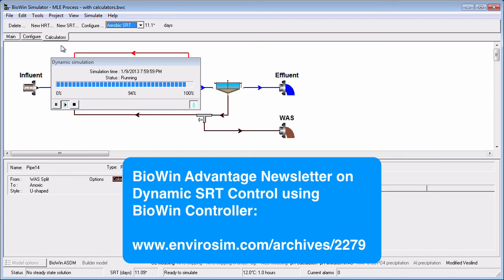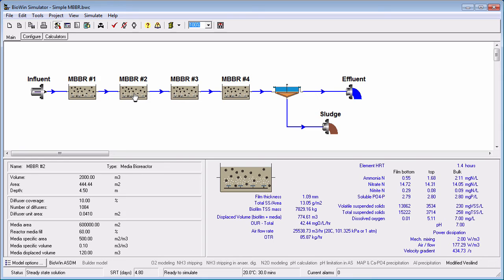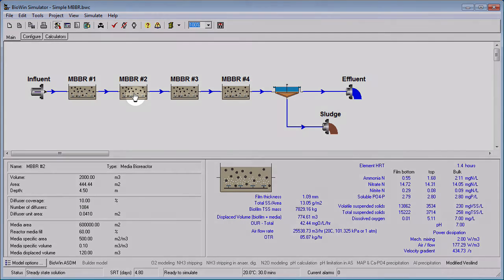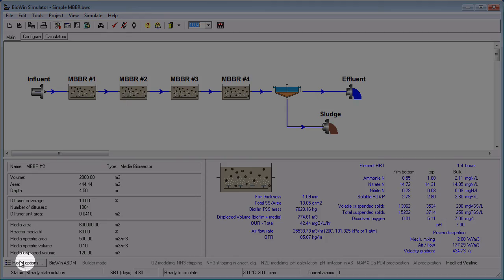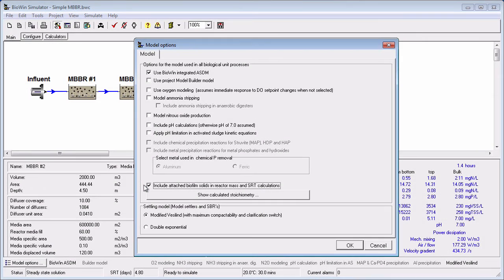Check out the BioWin Advantage newsletter that has been written on how to do this. If you are working with an attached growth system such as an IFAS or MBBR flowsheet, you can choose whether or not you want to include the attached biomass in the SRT calculation. In many cases, it is the SRT of the bulk solids that is of interest. To have BioWin calculate the SRT based on the bulk solids only, click on the Model Options button at the lower left corner of the main BioWin window, and deselect the option to include attached biofilm solids in the SRT calculation.